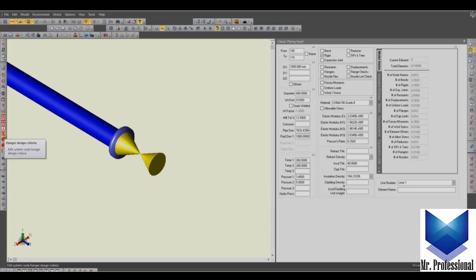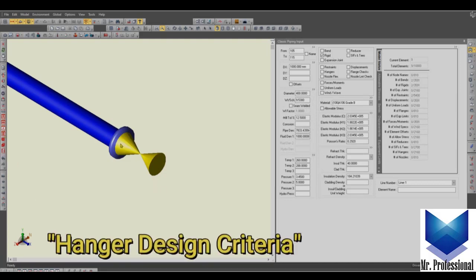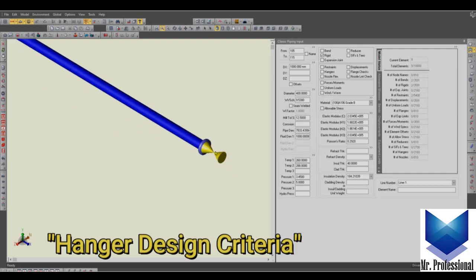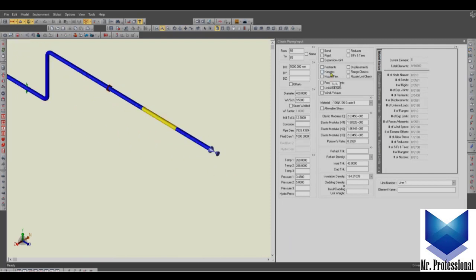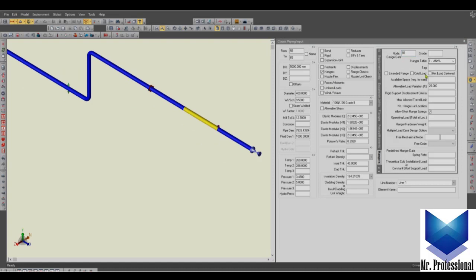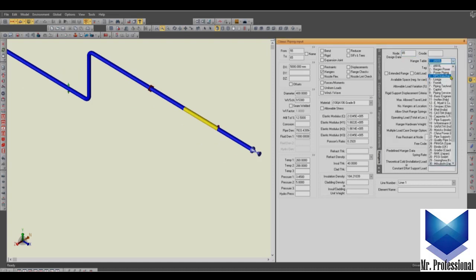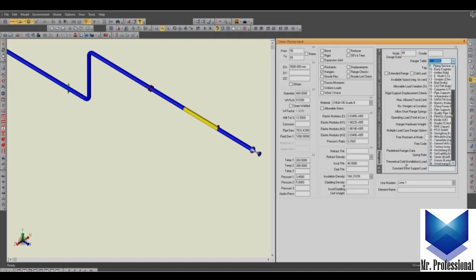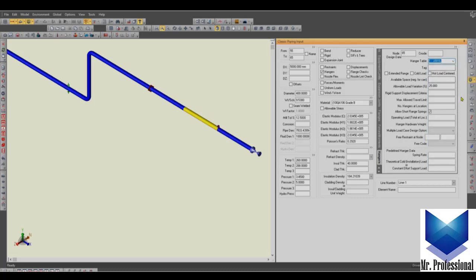The hanger design criteria, I prefer to use this option, hangers. Then you can select all the manufacturers that we find here on this list, and the spring rate of the support, let's say 33 newton per millimeter.